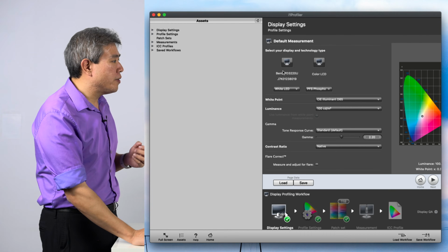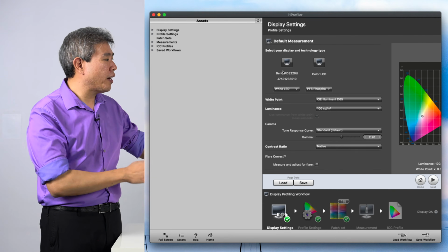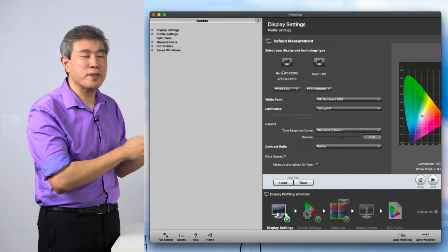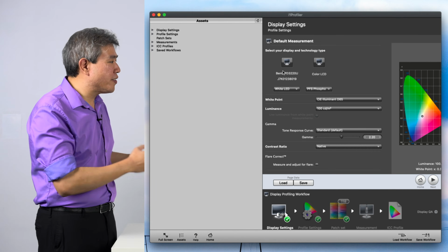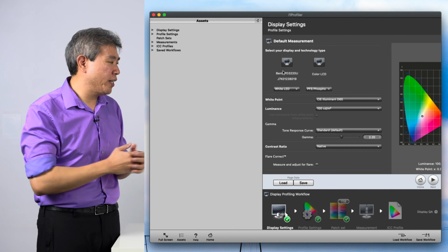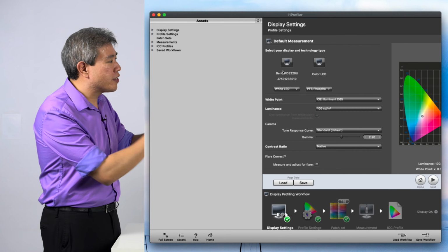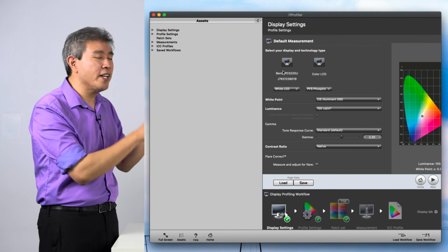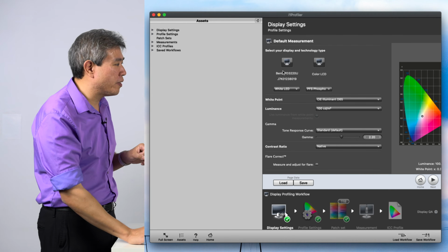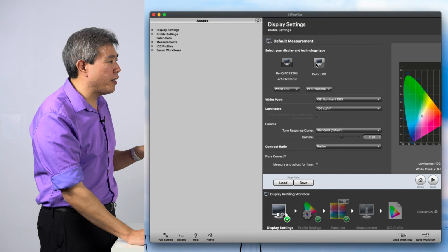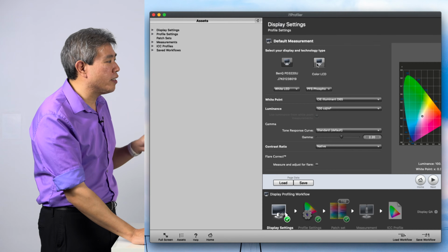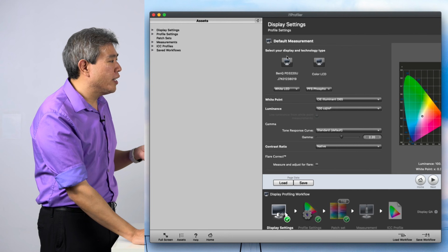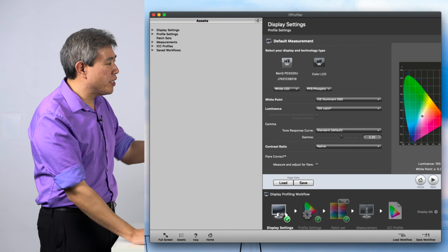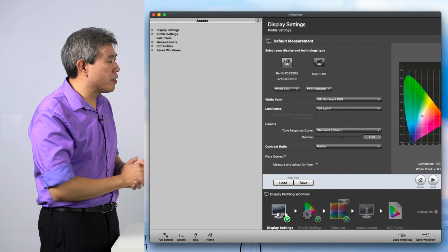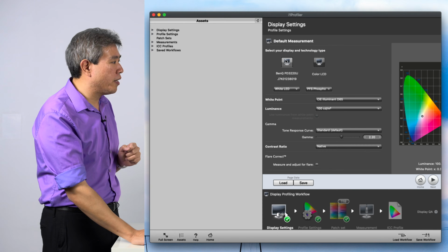The first thing we're going to do here is make sure that the i1Profiler screen is popping up on the correct display. This is the scenario when you have multiple displays hooked up to your system, because the screen that the i1Profiler is on is the screen that is actually doing the calibration. If you want to move i1Profiler to the other screen, you can simply click on the display that you want to calibrate. In this case, I already have this screen on the BenQ PD3220U. I am going to leave it here.